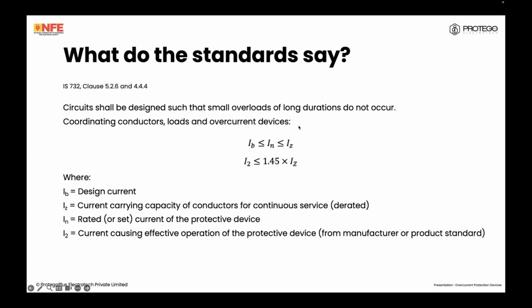This derating is important because electricians on site often say that if it's a 2.5 square mm cable, it can carry 20 amps. And they will just say 20 amps is greater than 16 amps or greater than 13 amps, so the inequality is satisfied. No. We need to ensure that it is greater than or equal to IN after derating. And also, I2 shall be lesser than or equal to 1.45 times IZ.